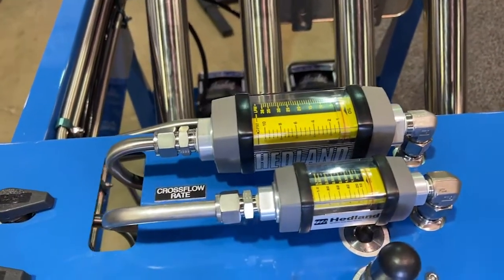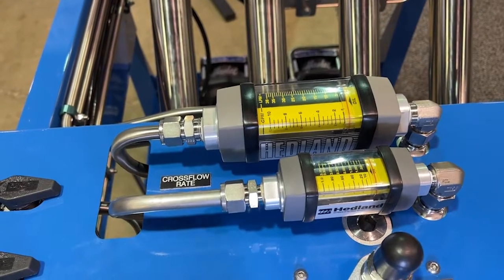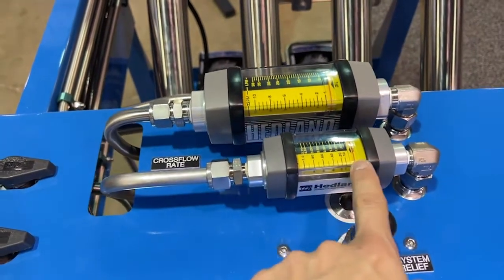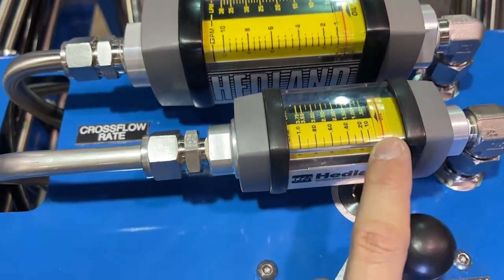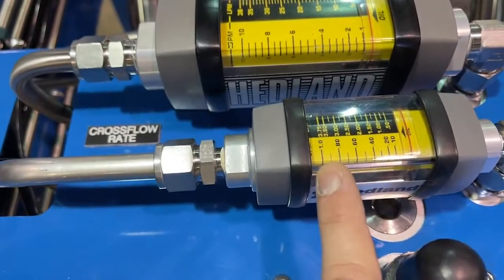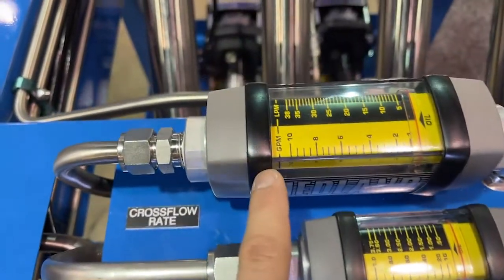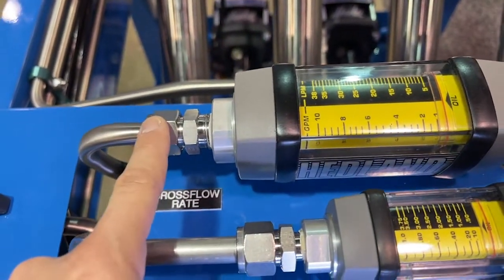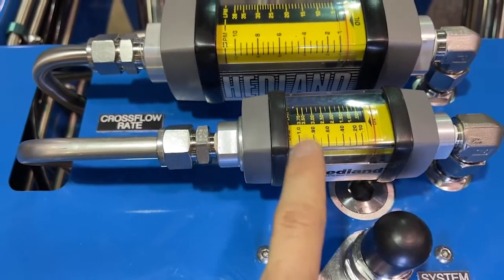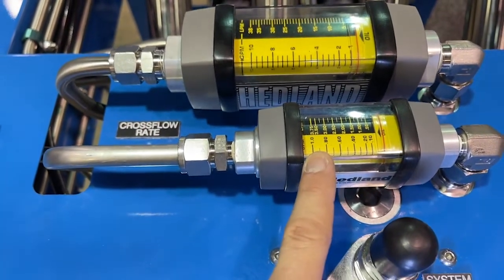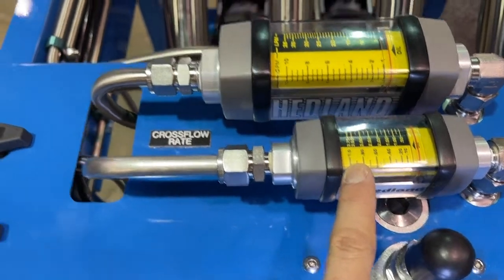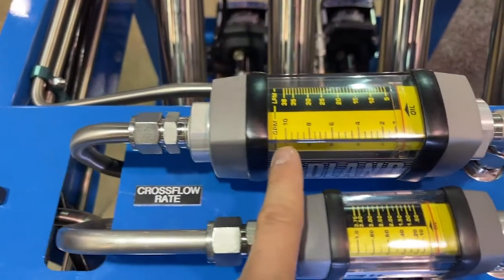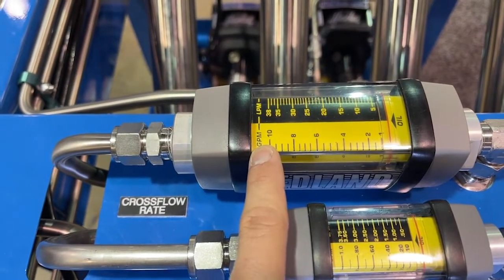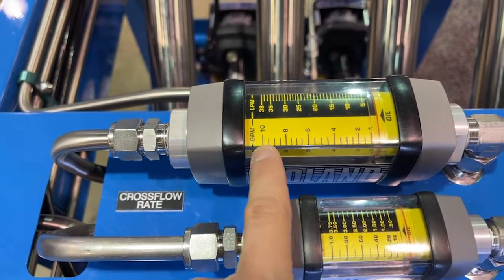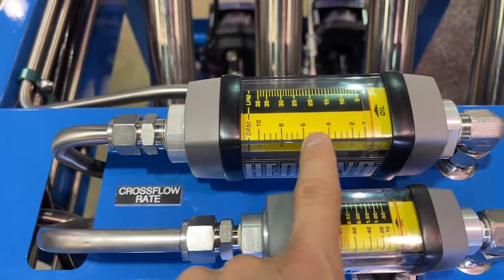These are flow meters, and you can see the little lines, and it'll tell you 1 gallon per minute. And then this is the crossflow filter. This is your flow rate. So 1 gallon per minute is 60 gallons per hour. And then your crossflow, we can measure up to 38 liters per minute or 10 gallons per minute. And like I said, you're going to be around these ranges.